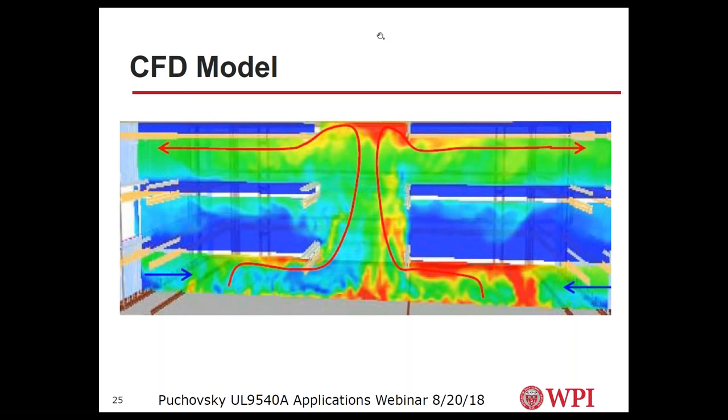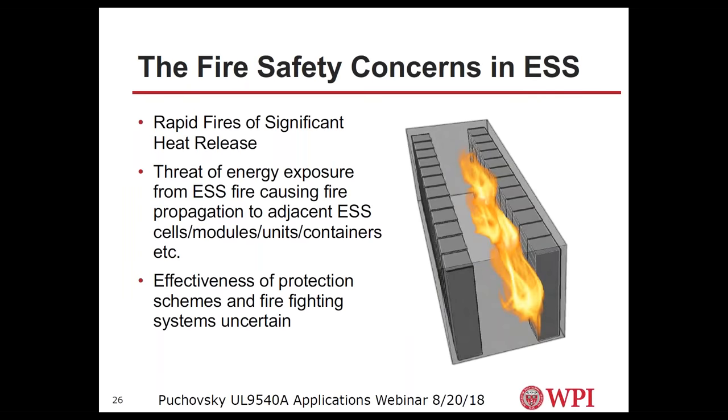We have pretty good confidence with that. Once we try to use the CFD model to actually model fire growth, we're less confident. We're also less confident in terms of how this type of model, if we actually enter a suppression system, would interact with the fire, to determine the effect of that suppression system on that particular fire. Our understanding of the physical phenomenon isn't quite where it needs to be to have a great deal of confidence in this particular method using a CFD model.